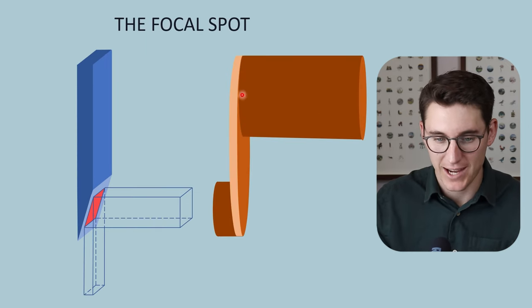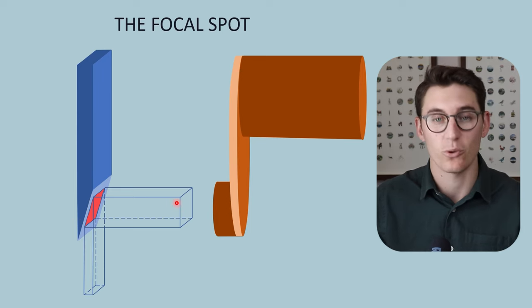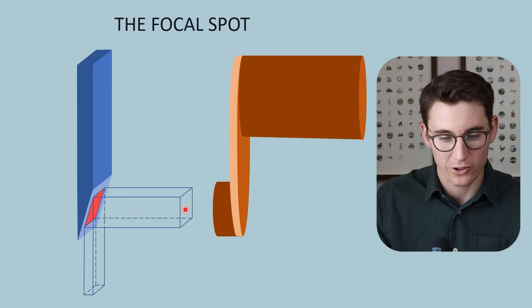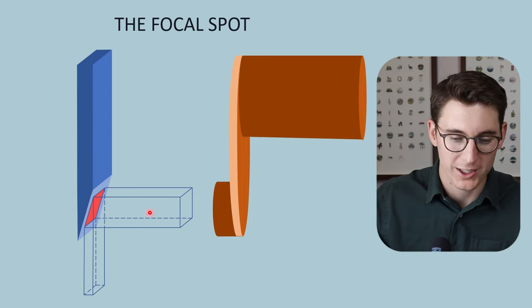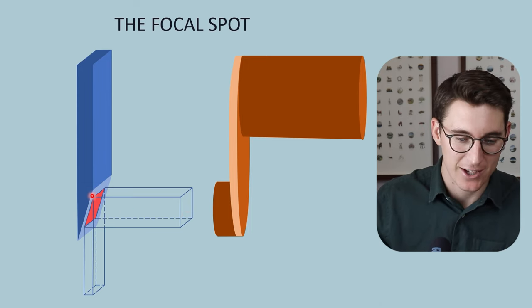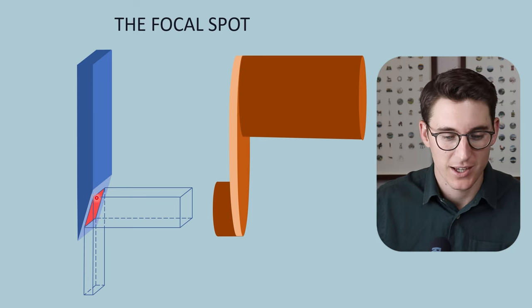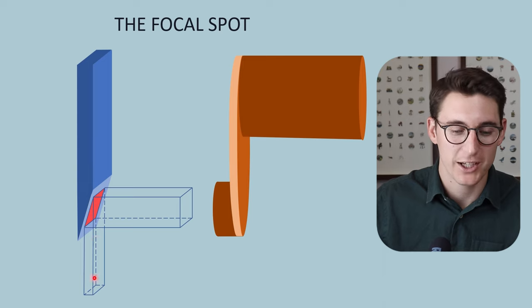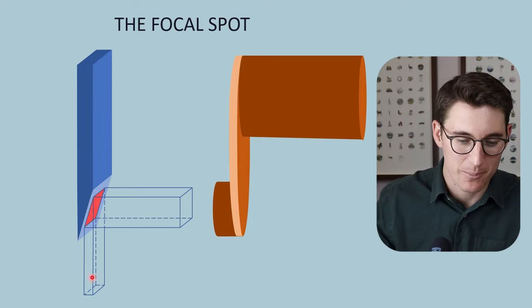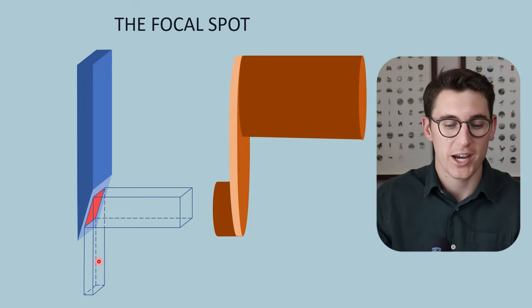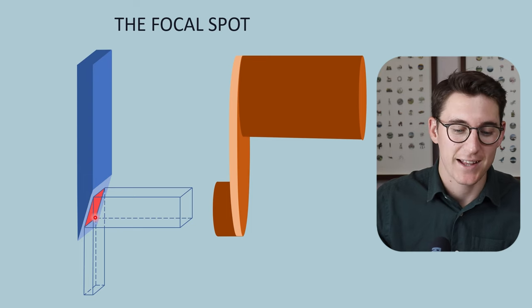Looking at a simplified diagram, we have our cathode which has produced electrons being accelerated towards our anode — I've used just the bottom half of the anode here. The first cuboid going from the cathode towards the anode represents our electron beam, also called the bombarding electron beam. Where those electrons strike the anode, that red region is known as the actual focal spot — where x-rays and heat are produced. The x-rays then head out towards our patient, represented by our effective focal spot.